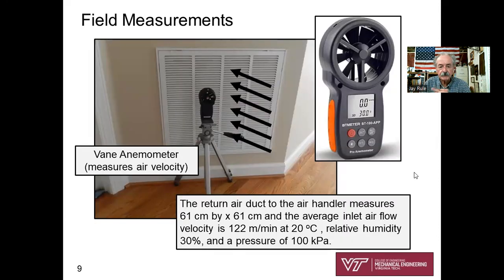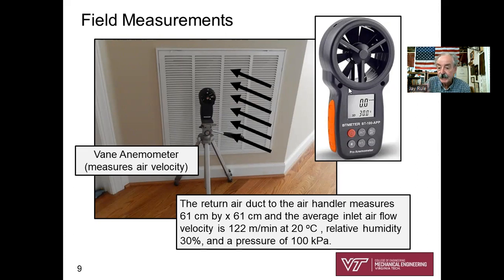You may ask how those numbers were obtained — here's a photograph showing how. I set up a vane anemometer at the return air inlet duct, which spins based on the velocity of air passing through it. I measured the inlet duct dimensions and used the anemometer to get 122 meters per minute.